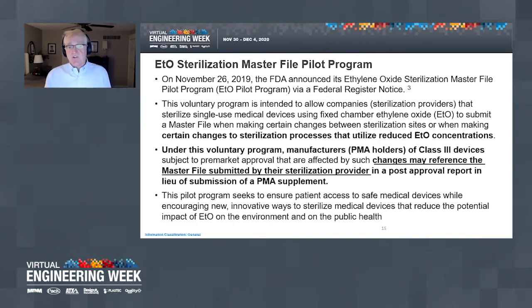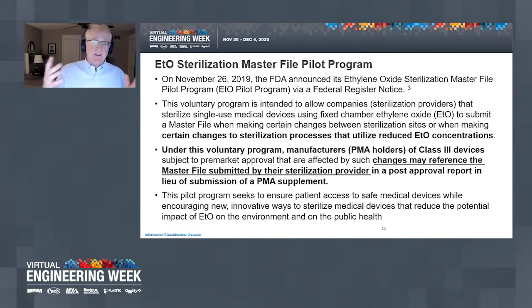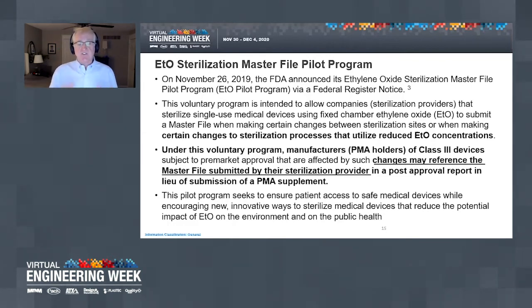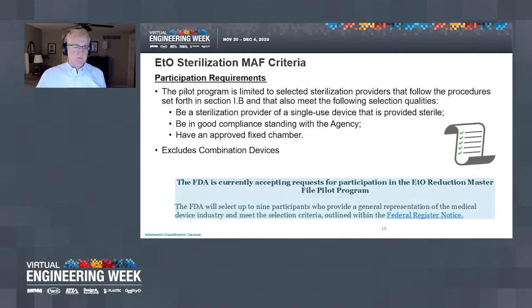Now, if and when a contract sterilizer is accepted into this program and your company happens to use them, and I'll say Sterigenics, I've presented with, not Sterigenics, Steris is a really quite a large contract sterilizer. We work with them. I just presented with them last month, and they're very engaged and very happy and eager to work with you to reduce the EO in your cycles, get through the validation process, and assist you in any way they can. And of course, using that, they as a holder can authorize you as an OEM to annual report this for your PMA and reference their master file number. So that in a nutshell is the value of the master files. You get away from the submission burden and you can just annual report and move forward.